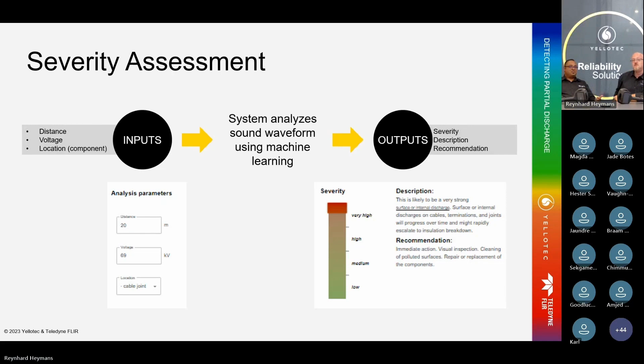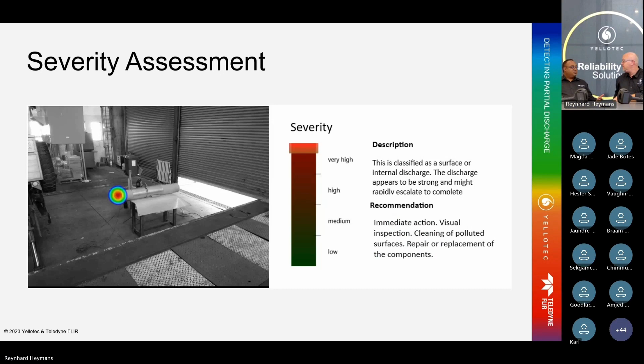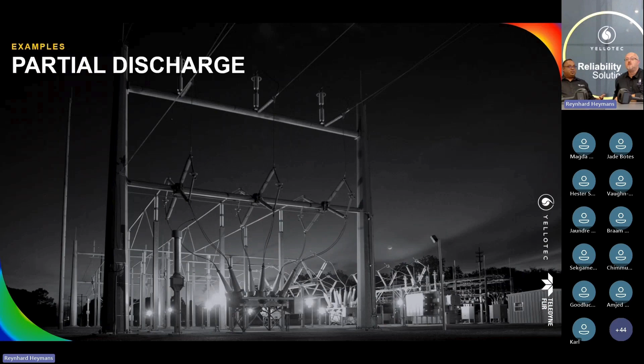So this was done under controlled circumstances. If you look here, we're simulating a fault. Okay, this was an internal cable fault that we were trying to simulate, or that we did simulate. And as you see, the first thing it tells you is severity level: very high. Okay, here's the description. It starts to classify the discharge, and it gives you some form of recommendation. Obviously, immediate action in this case, due to the fact that it's high severity. Excellent.